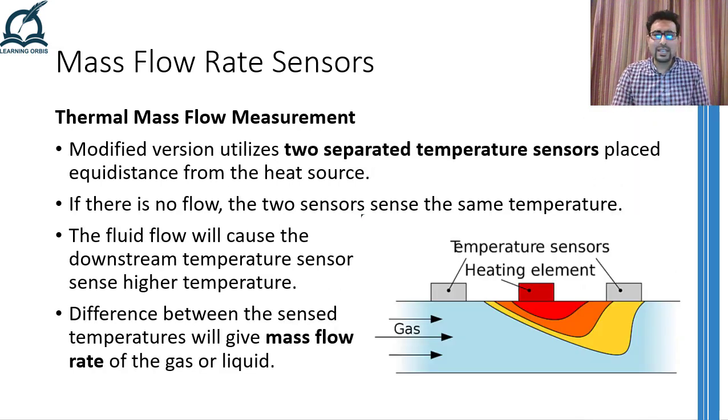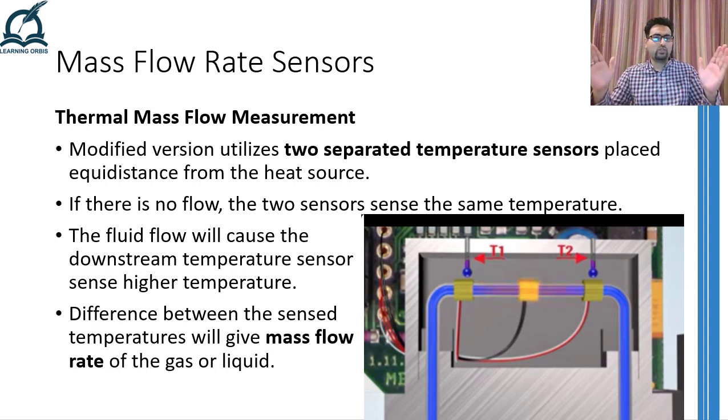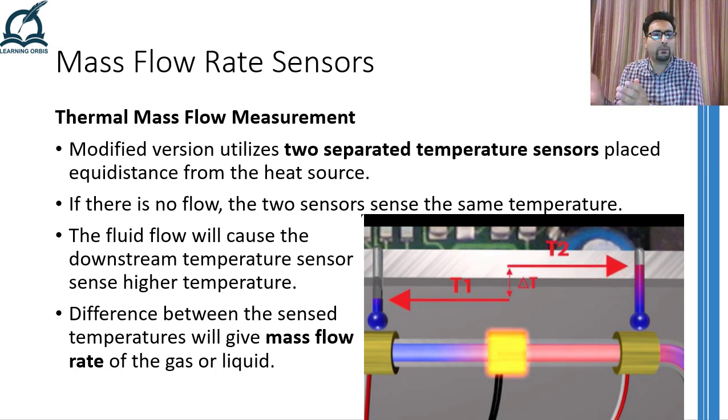In a modified version of this sensor, which is specially designed for liquids, two separate temperature sensors are placed equidistant from the heater. One upstream and the other one downstream as shown over here. If there is no flow in the pipe, then the heat from the heater will disperse equally on all sides. Hence both temperature sensors are going to read the same temperature. However, if there is some flow in the pipe, then the fluid particles will take the heat from the heater towards the sensor which is installed downstream. Hence the downstream sensor will sense higher temperature, whereas the upstream sensor will sense a lower temperature. This temperature difference between the two sensors will now be directly proportional to the mass flow rate.